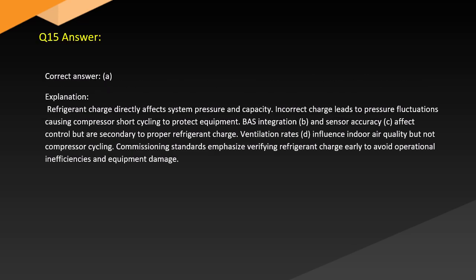Answer. Correct answer. A. Explanation. Refrigerant charge directly affects system pressure and capacity. Incorrect charge leads to pressure fluctuations causing compressor short cycling to protect equipment. BAS integration, B, and sensor accuracy, C, affect control but are secondary to proper refrigerant charge. Ventilation rates, D, influence indoor air quality but not compressor cycling. Commissioning standards emphasize verifying refrigerant charge early to avoid operational inefficiencies and equipment damage.